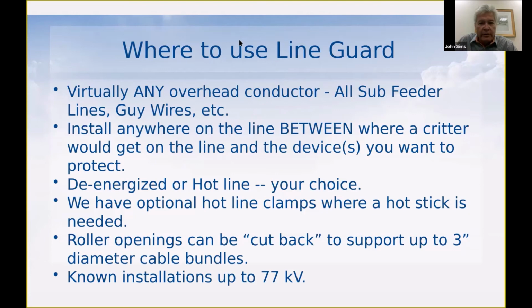The rollers are a conical shape, and those rollers can actually be cut back. So if you had, for instance, a triplex line, more like a cable bundle than an individual conductor, it still works fine. Those roller openings can be cut back with a simple chop saw, shaving off a quarter inch or even up to half an inch on each end before installing, which opens it up to support up to a 3-inch cable bundle. Then you fasten it to the line using your choice of clamps, or the ones we supply with the system.